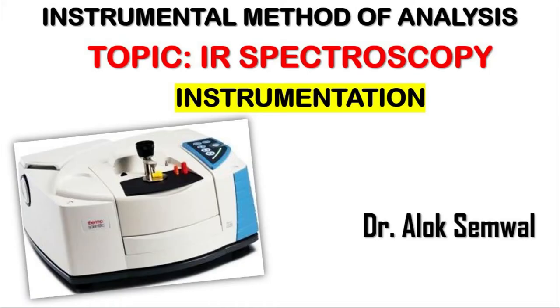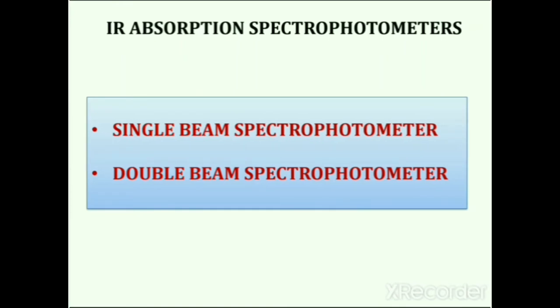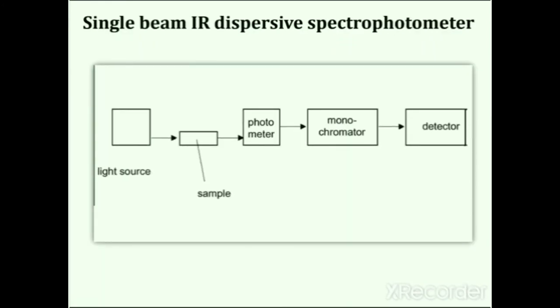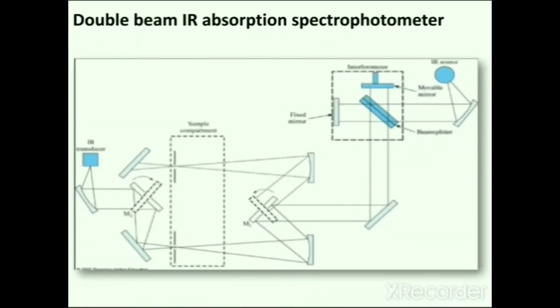Next topic is instrumentation of infrared spectroscopy. Infrared spectrophotometers are of two types: single beam and double beam spectrophotometers. A single beam spectrophotometer uses a single beam of light passing through one solution at a time. In a double beam instrument, a single beam splits into two — one passes through the sample, another through the reference. Modern dispersive IR spectrophotometers are invariably double beam instruments. Radiation starts from the light source, is incident upon the sample, goes to the monochromator, and then to the detector. This is a double beam scanning IR instrument using a diffraction grating in a monochromator to disperse different wavelengths.